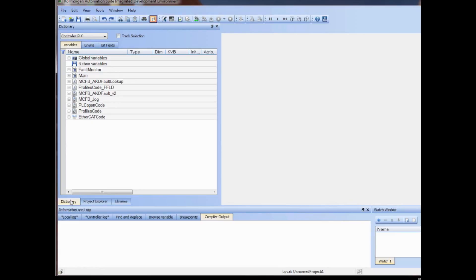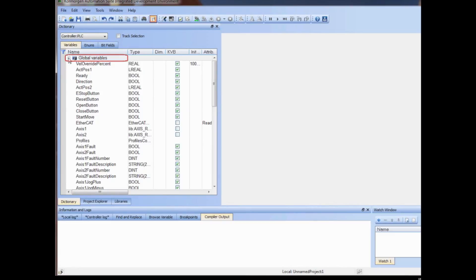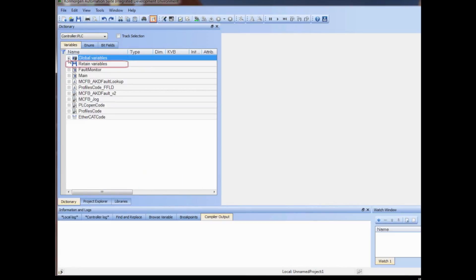When a new project template is opened, the dictionary contains variables that support the features within the template. Variables have a range of use, or scope. Scope options are global variables, which can be used in any program or sub-program in the project, and retain variables, which are also global variables in which the latest value is saved when the controller is turned off.